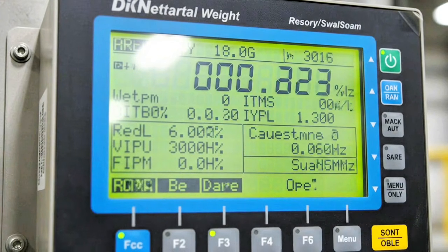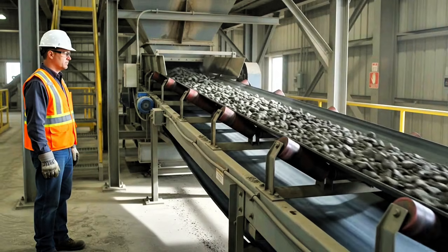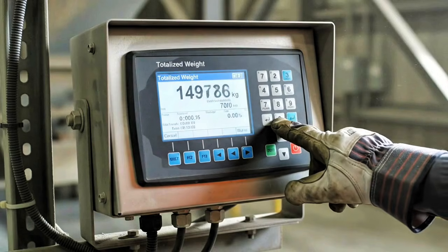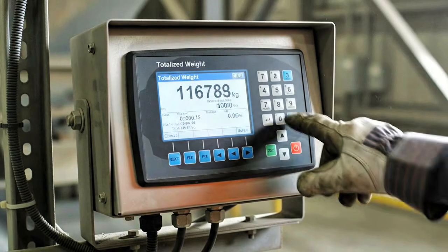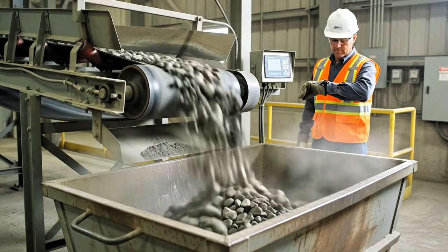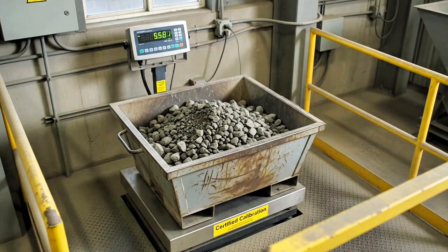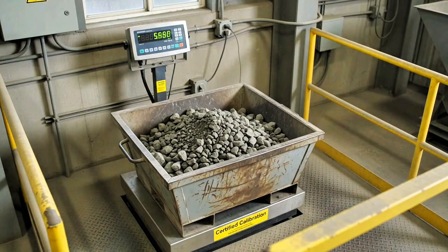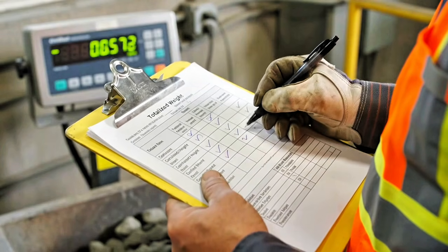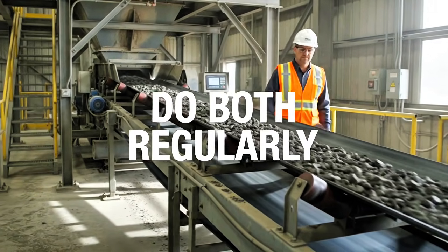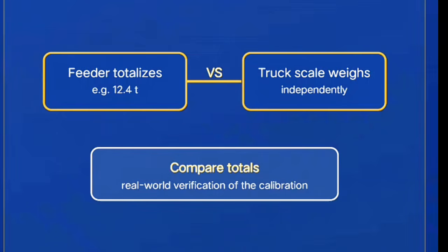The other dynamic method is a material test, running actual material over the feeder for a set time or set totalized weight, then physically weighing that material on an independent scale, like a certified truck scale or platform scale, and comparing it against what the feeder totalized. This is the real-world check, and honestly, I recommend doing both: chain calibration to set the feeder up correctly, and periodic material tests to verify it's holding that calibration in actual operating conditions.